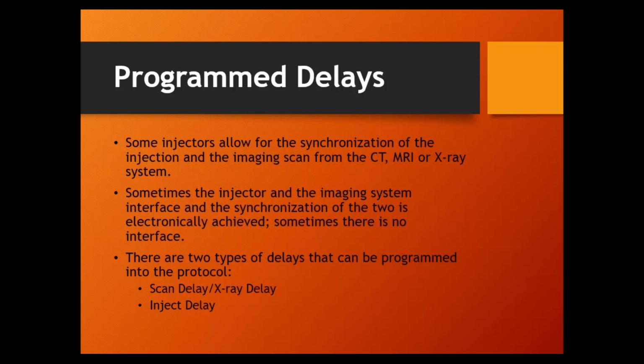we'll assume that the systems are not talking to each other, meaning the injector and the X-ray system are not talking to each other. You have 2 buttons you have to hit. You have to hit X-ray exposure, and you have to hit inject switch, right? If I want there to be a 2-second delay of the injector, if I don't program in the delay, I have to hit the exposure switch, 1 Mississippi, 2 Mississippi, then hit the inject switch, right? It lacks precision, right? So what we can do is program in 2-second injector.